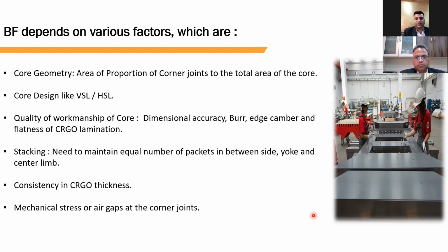There is also a hot question with every transformer manufacturer: which is the best design? Technically, I can say vertical steplap is the best design, because in vertical the alignment of the CRGO will be proper, done with the help of guide holes. In vertical steplap, guide holes are mandatory, because while inserting the yoke plates, we need the guide hole, otherwise the yoke plate will not align with the limbs.